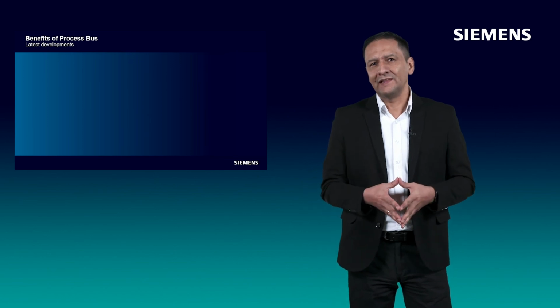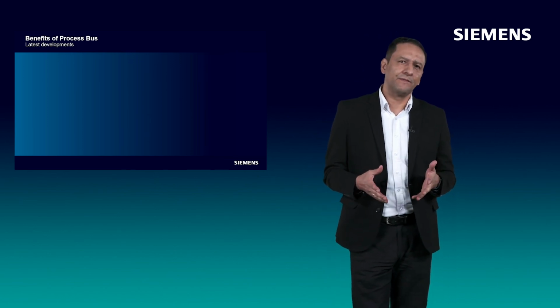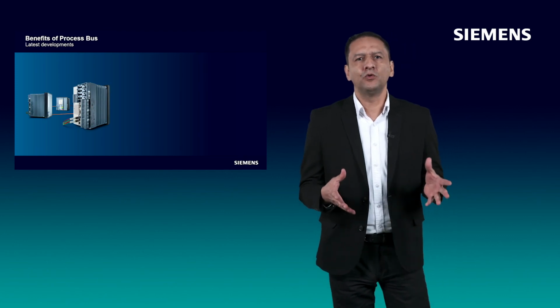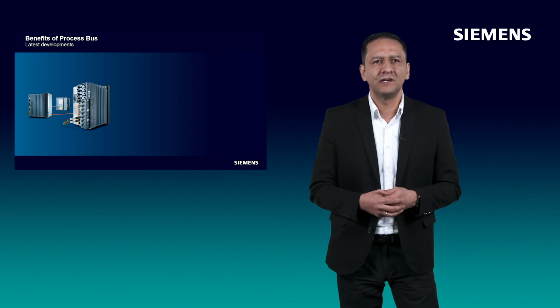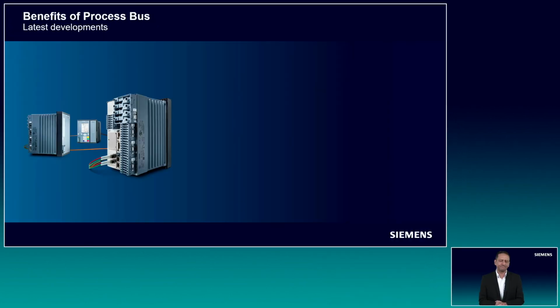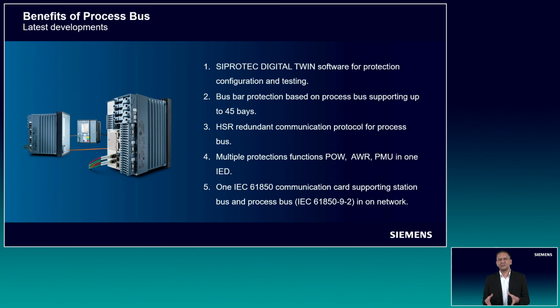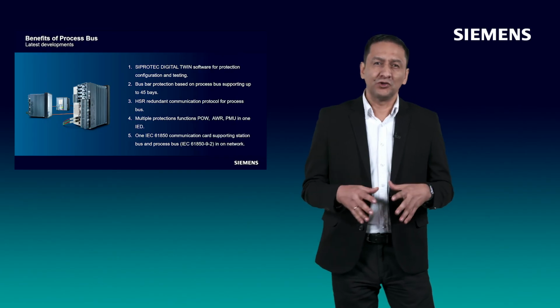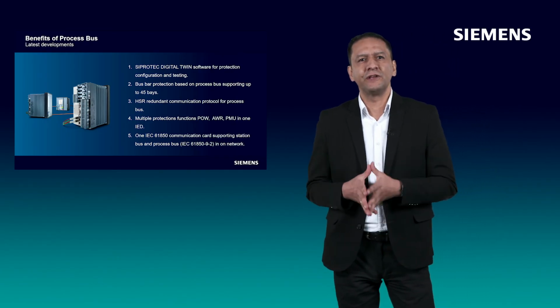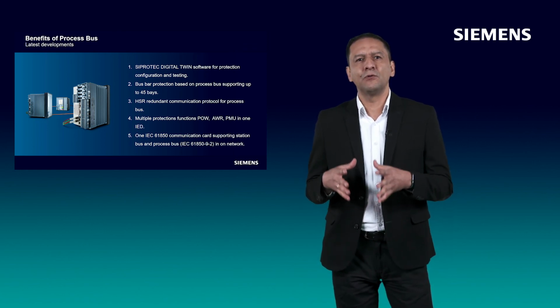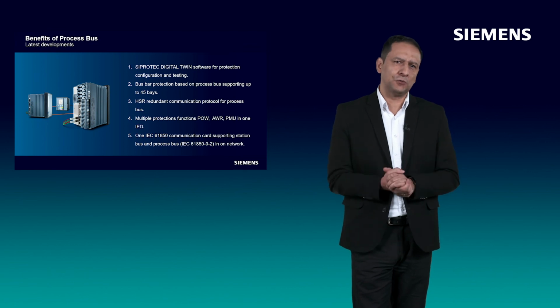As an overview, let's take a look at our latest developments for process bus, which will help even more to optimize our process bus-based protection solutions and further contribute to cost savings. First, we have the SIPROTEC Digital Twin software, which substitutes our SIPROTEC 5 protection relays and enables testing relay configuration without having a physical relay on the table. We have released busbar protection based on process bus, which supports up to 45 bays. Also, now for process bus, we support HSR communication ring topology. In this way, we will be able to reduce the number of switches needed to connect merging units.